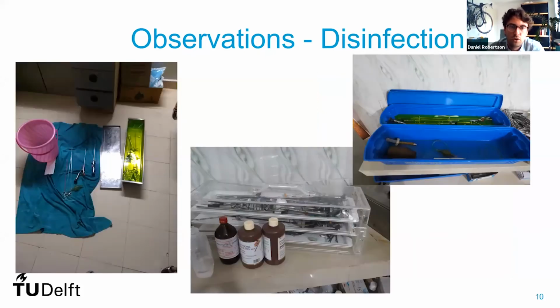And the other observation that we saw was that, as I mentioned before, the laparoscopic instruments were mostly treated with high-level disinfection instead of steam sterilization. So only disinfectants are used. And I will explain some of this later, but these disinfectants need careful monitoring and checking to see if they are still effective. But no one really knew about this, and there was no knowledge about the limitations of these disinfectants.